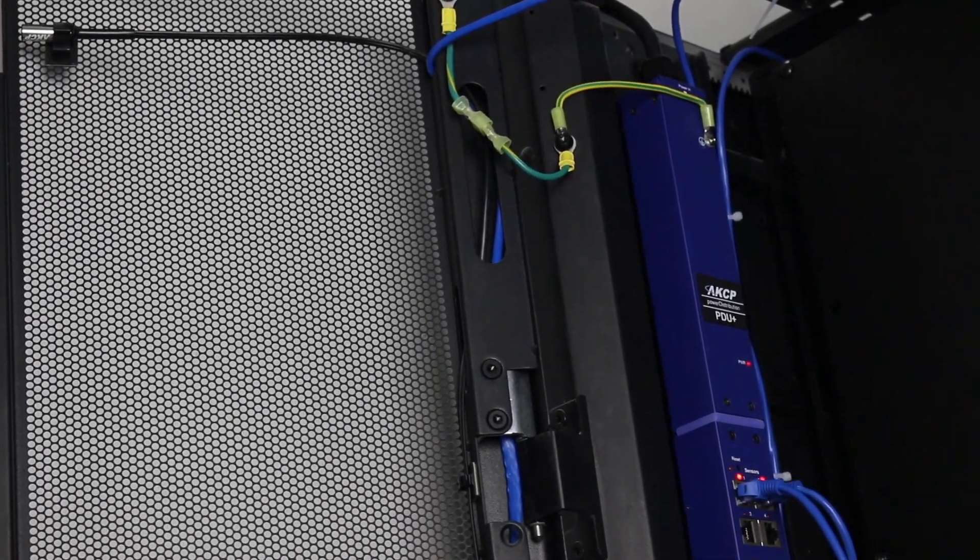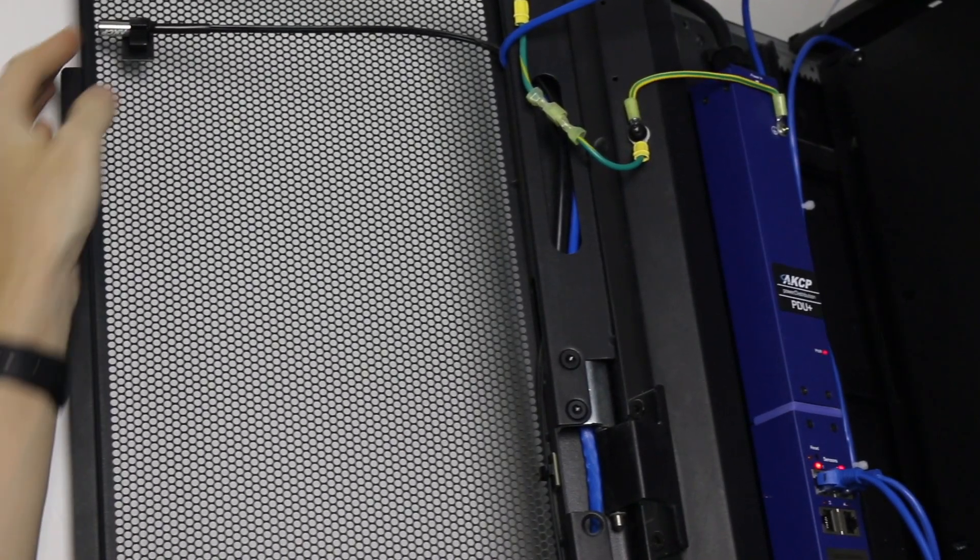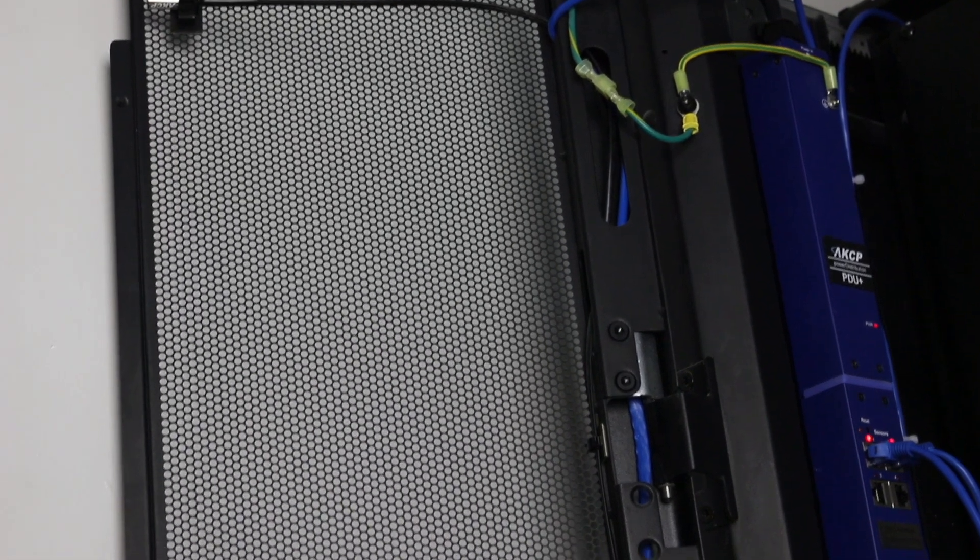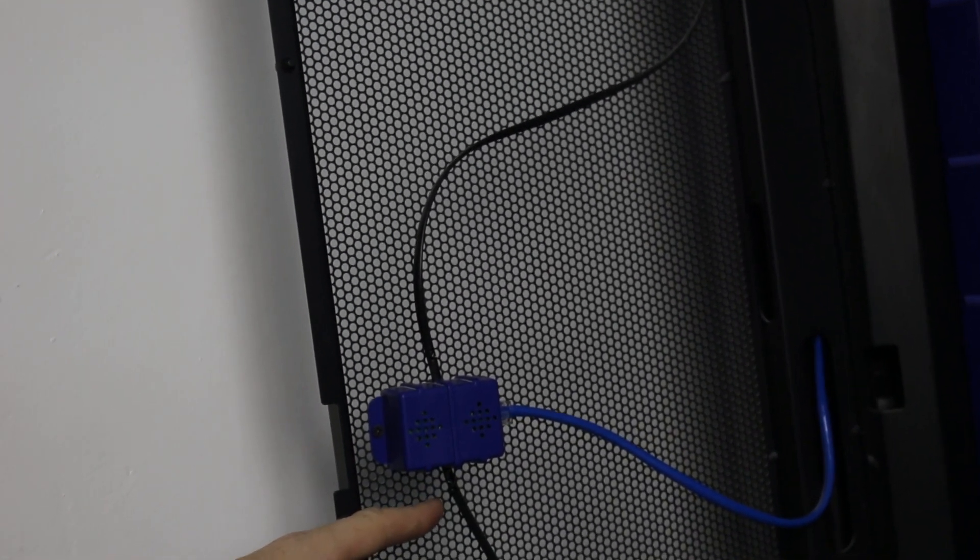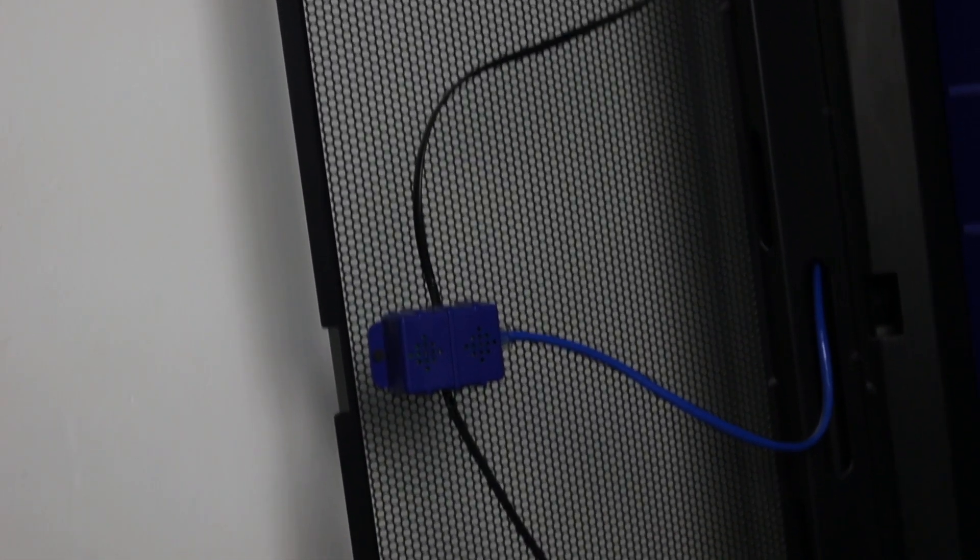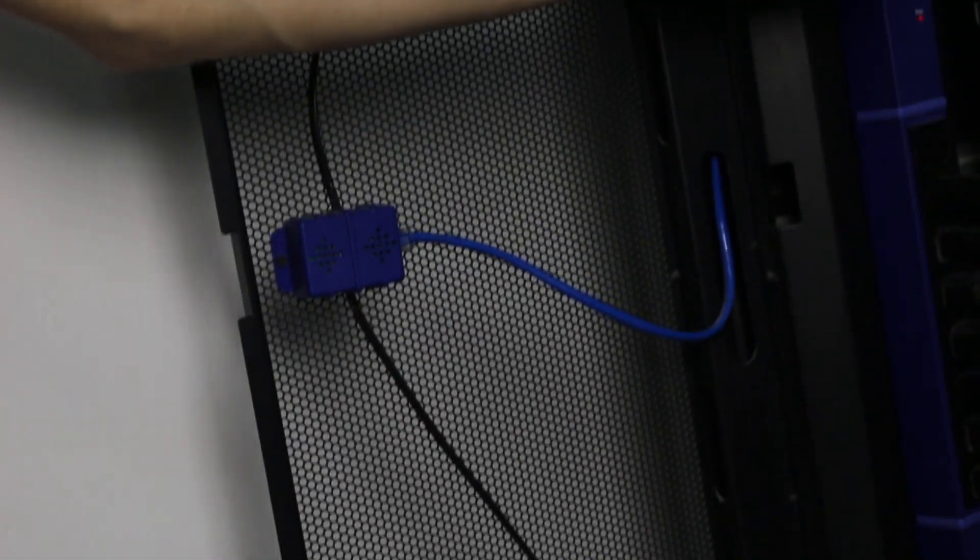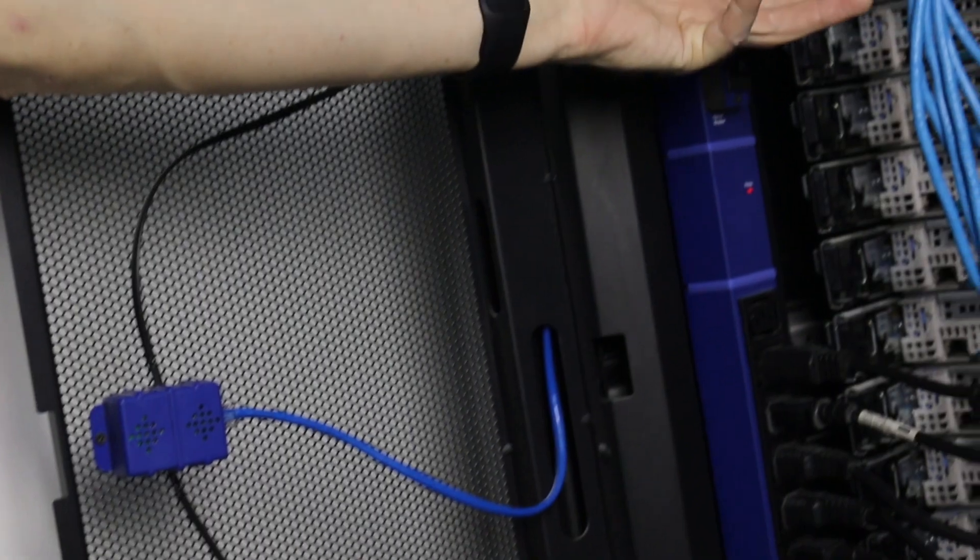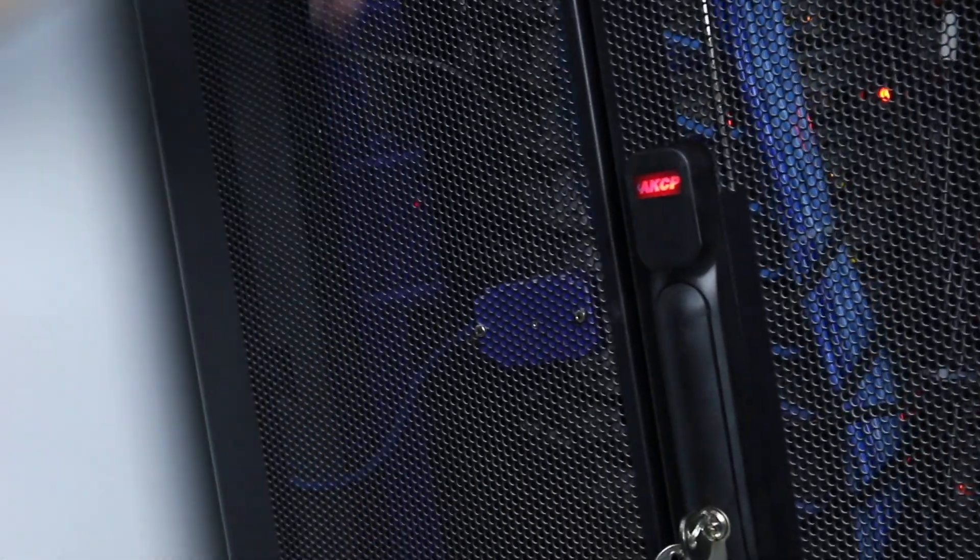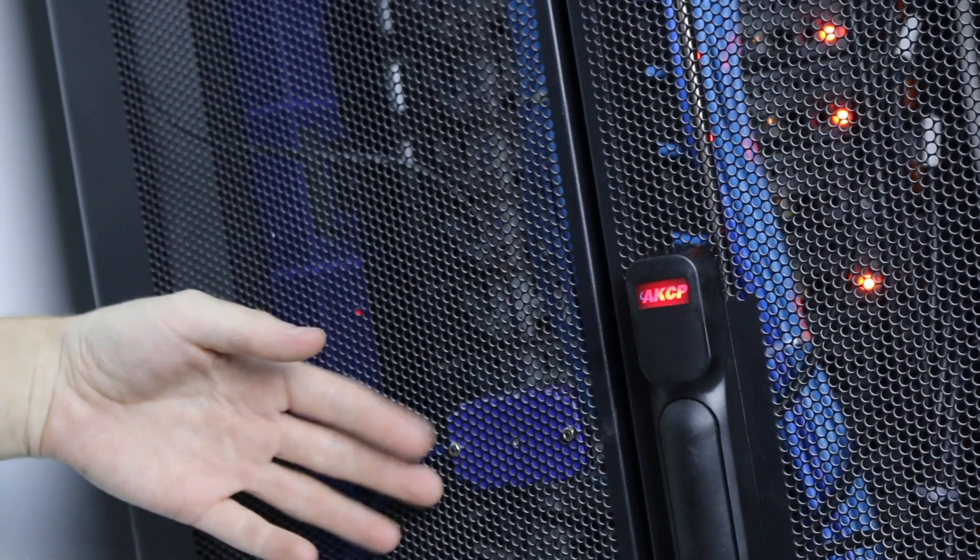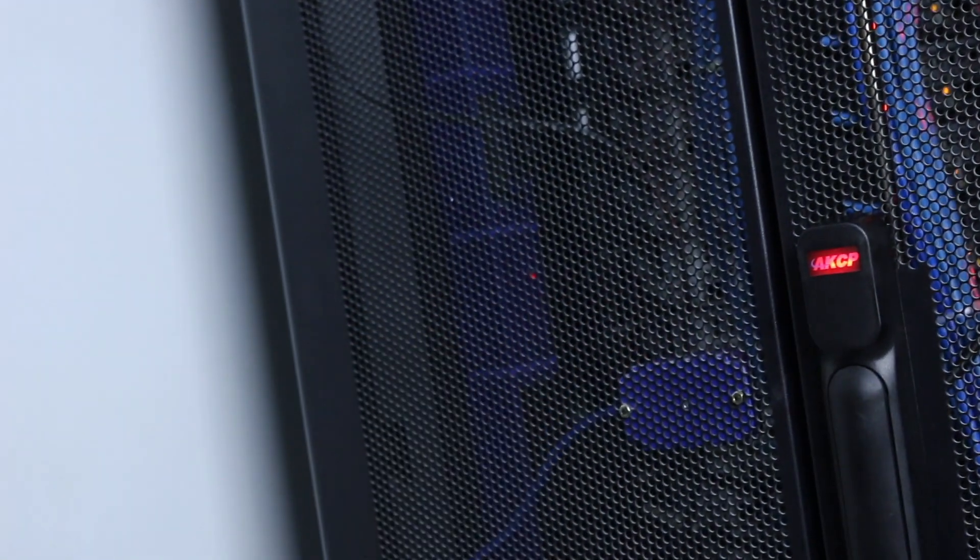At the rear of the cabinet we have the same thing. We've got our temperature sensor at the top, a temperature-humidity sensor positioned at the middle of the rear door, and a temperature sensor at the bottom. This is a perforated rear door. The hot air from the servers is being expelled through the rear, so when this door is closed, the hot air is measured as it passes through the perforated rear door.